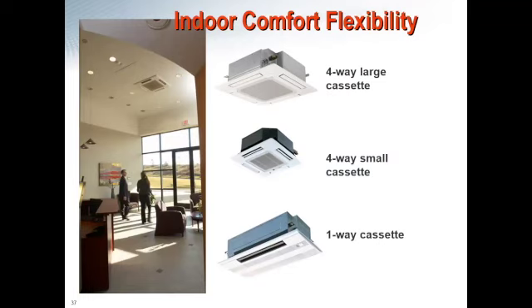Lastly, here on the bottom, we also have that one-way cassette unit. This is a unit that's not seen as much, but it's something that's very valuable to VRF manufacturers. This is great for installations where you may want to wash windows, or in the case if you ever have to fit between two 16-inch on center ceiling joists for a residential application, these units are designed to fit in there exactly. So that's a really nice application for residential projects.